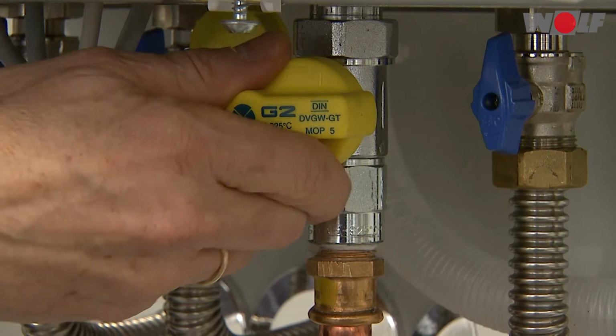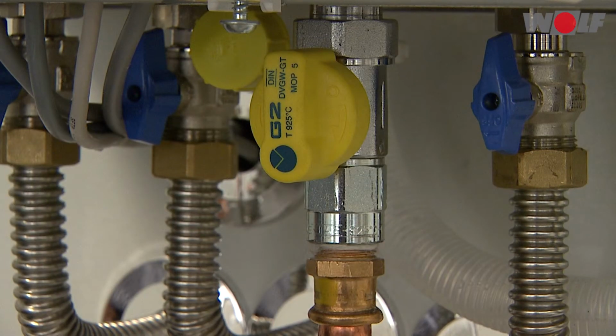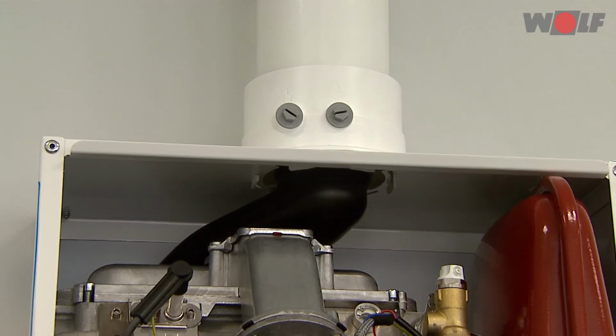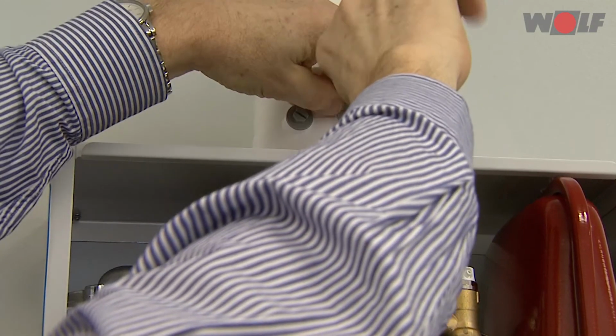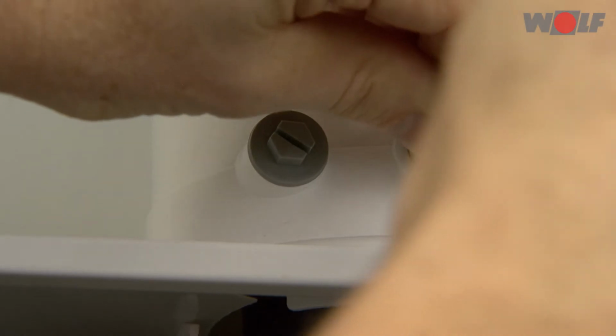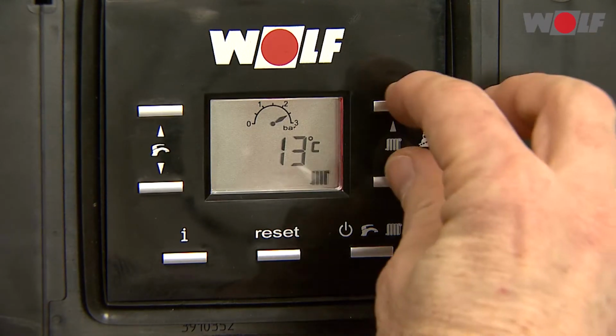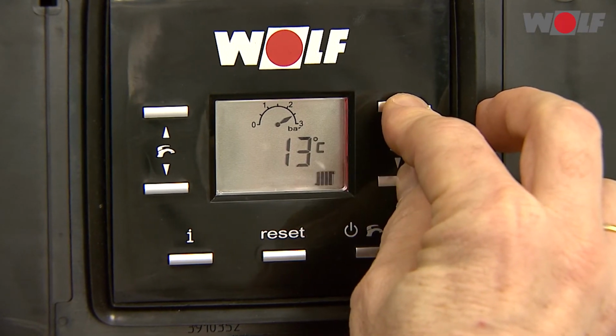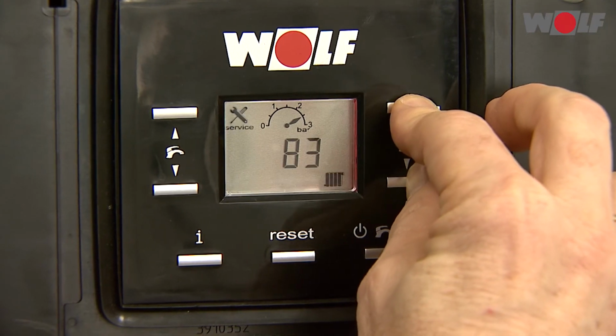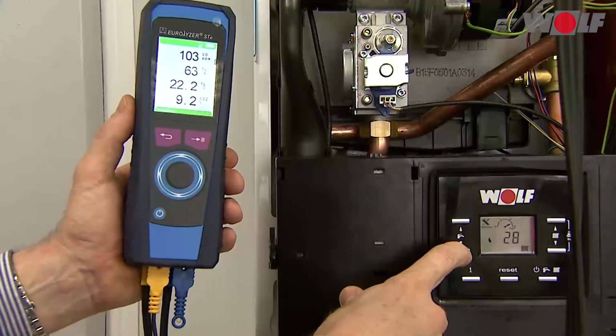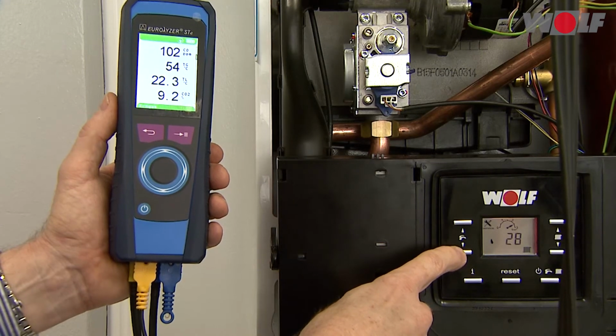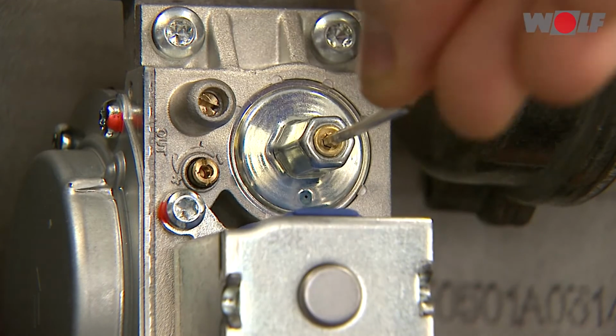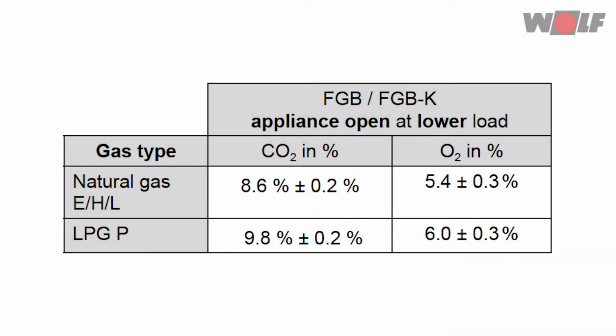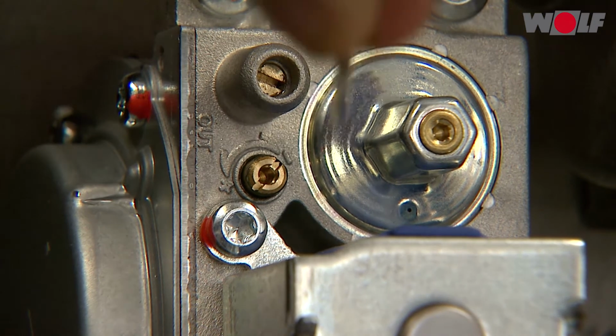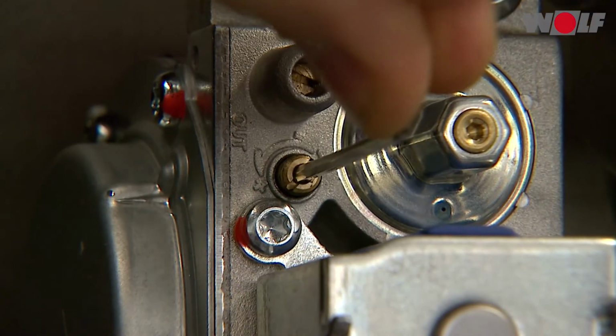Turn off the boiler, close the gas ball valve, remove the pressure gauge and tighten the screw in the gas test connector. Checking the flue gas parameters: open the gas ball valve and switch on the appliance. Check the gas pipe and hydraulics for tightness. Remove screw B from the right-hand test port. Insert the test probe. Switch on the boiler and enable the emissions test mode via buttons 6 and 7. Press and hold for 5 seconds. Carry out the checks after a minimum of 60 seconds of operation, measuring first at upper load and then at lower load. CO2 setting at lower load. CO2 setting value at upper load.